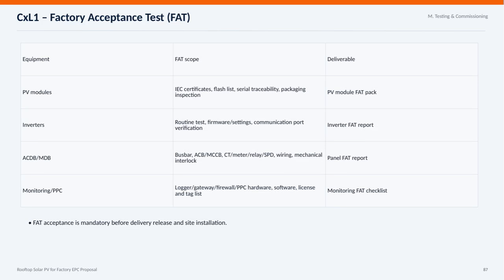Here we have the Factory Acceptance Test, or FAT, which is a crucial step before delivering and installing the rooftop solar PV system. The FAT ensures that all major equipment, like PV modules, inverters, ACDB and MDB panels, and the monitoring system, meet strict quality and performance standards. For PV modules, we check IEC certificates, flash lists, serial traceability, and packaging. Inverters undergo routine testing, firmware and settings verification, and communication checks. The panels are tested for bus bars, circuit breakers, meters, wiring, and mechanical interlocks, while the monitoring system is verified for hardware, software, licenses, and tags. FAT acceptance is mandatory before any equipment is released for delivery or installation, guaranteeing reliability and smooth commissioning.